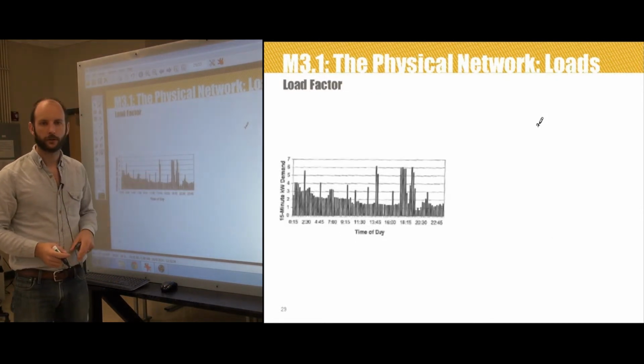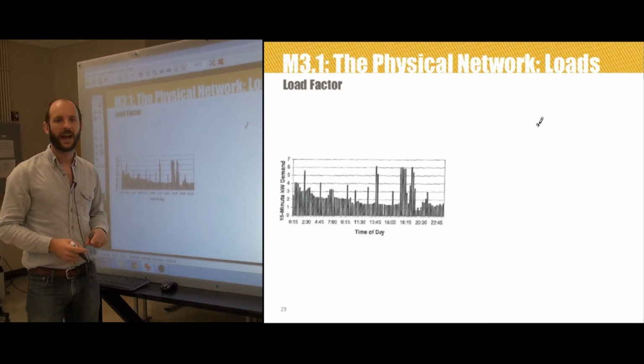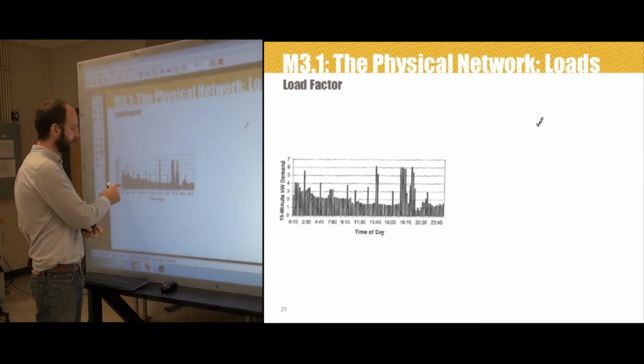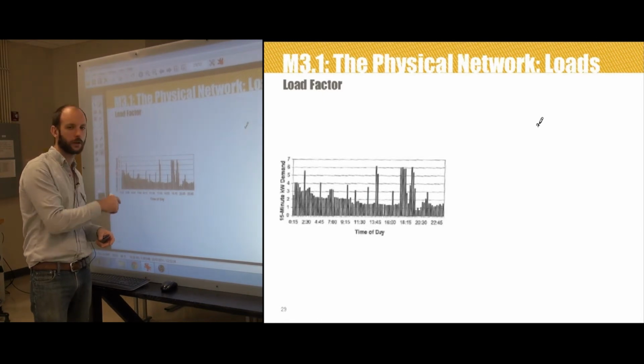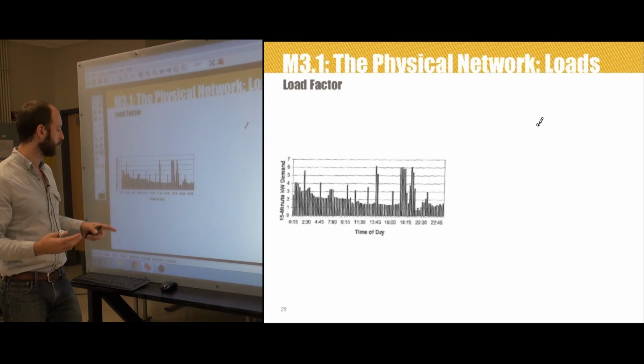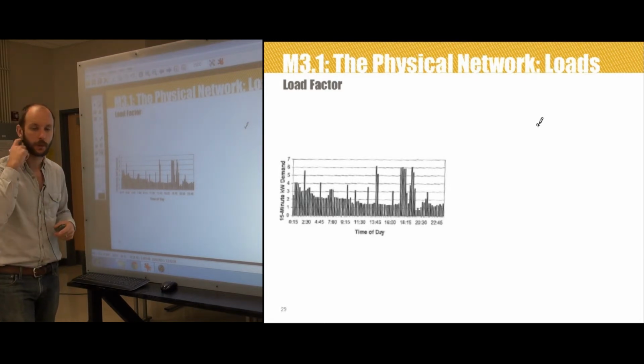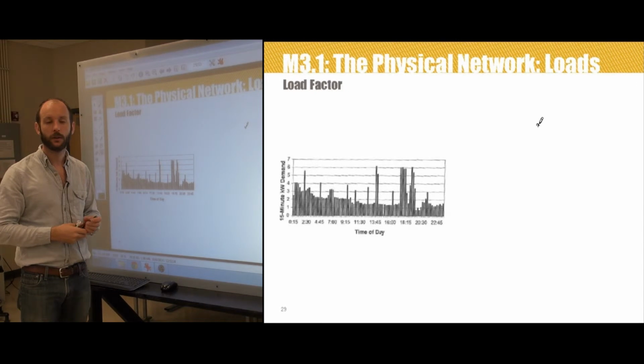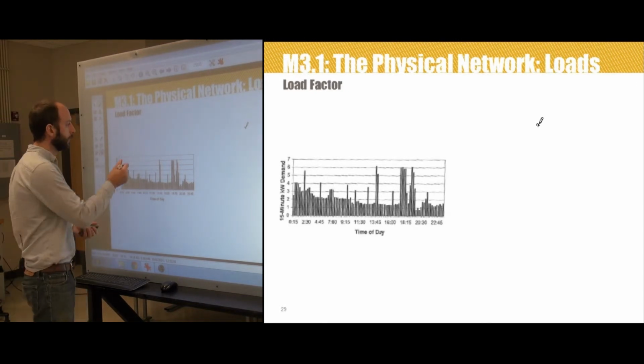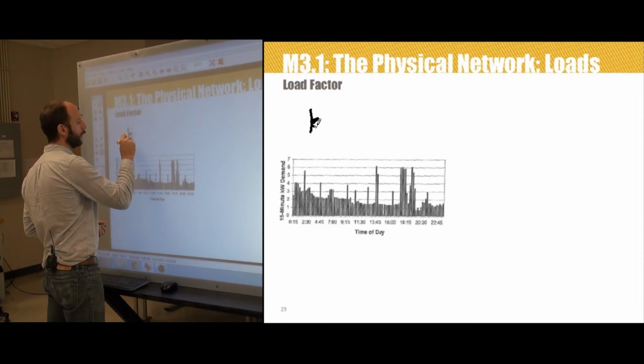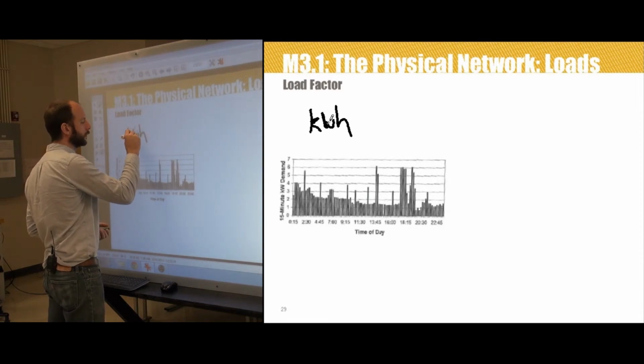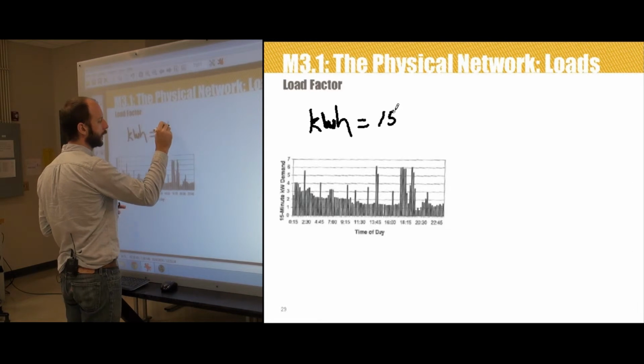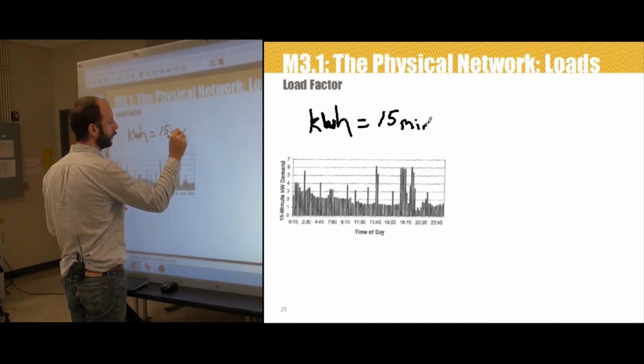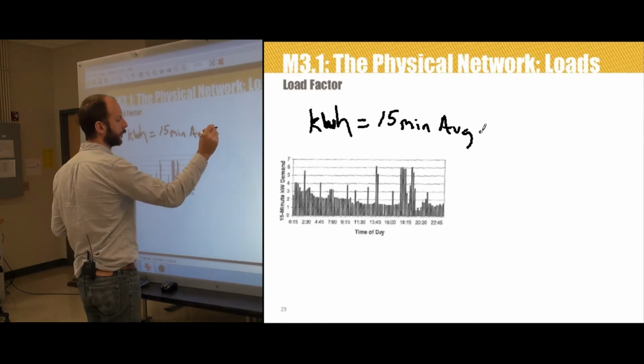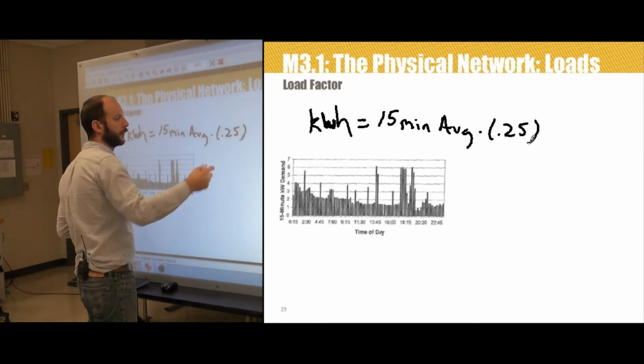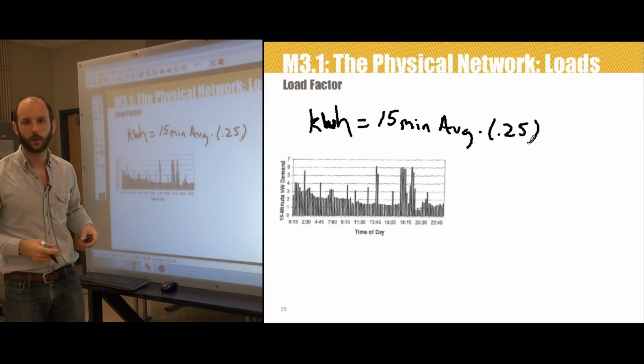And I've just recreated that graph right here. During this 24-hour period, energy is consumed, right? I can calculate how much energy is consumed by multiplying the 15-minute kilowatt demand, which is measured in kilowatts, by 0.25 if I want it in kilowatt hours, right? Because 15 minutes is a quarter of an hour. Kilowatt hours, or the energy usage, is just going to be the 15-minute average demand times 0.25, right? Because 15 divided by 60 is a quarter. That'll give me my energy in kilowatt hours.